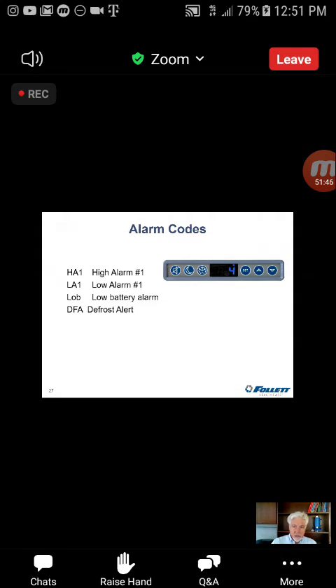Now, if for whatever reason the defrost time gets extended, there's a time limit on each unit, which we'll be showing you in just a moment. If it terminates on time, you'll get an alert to let you know that happened. And so a little investigation is called for to determine why that's going on.